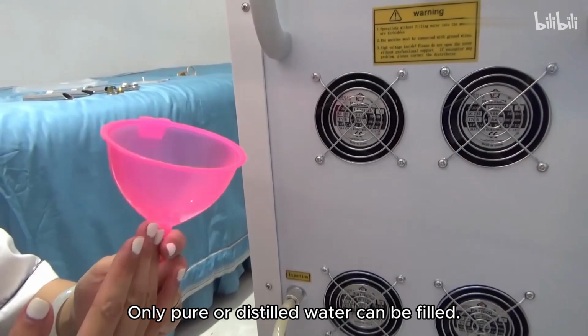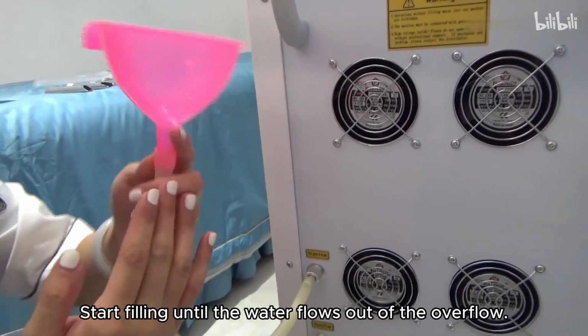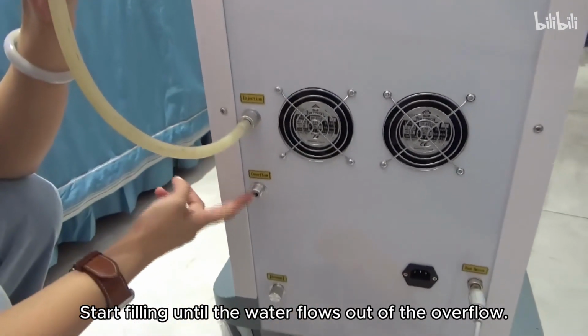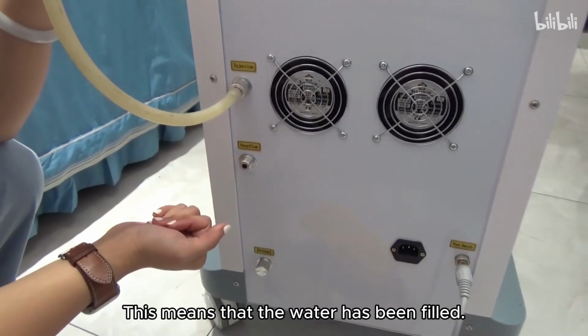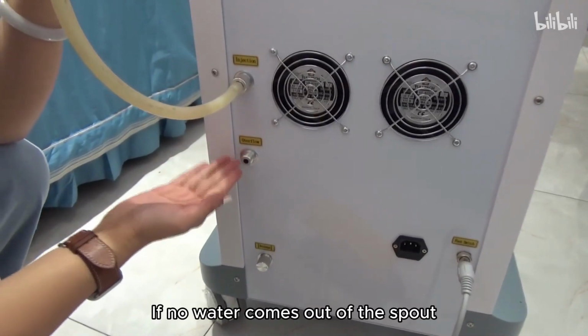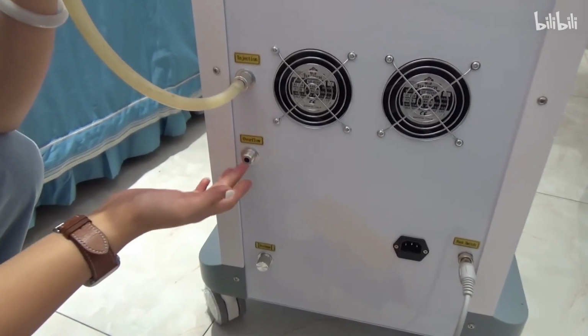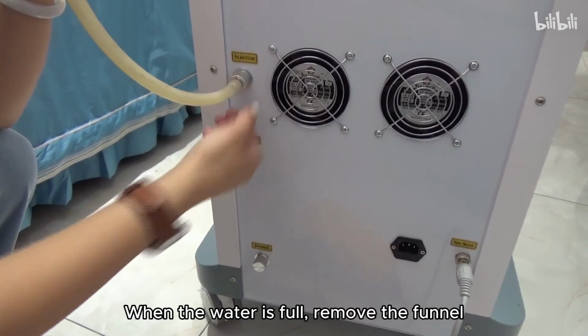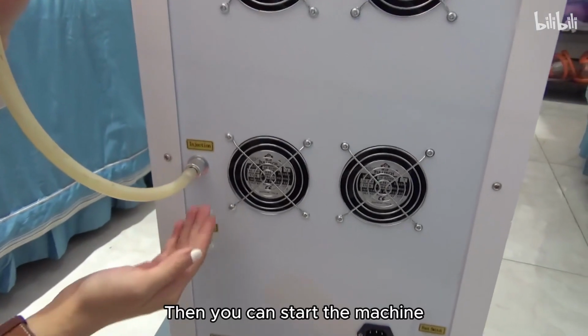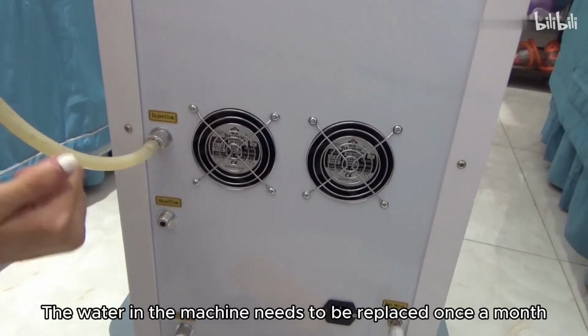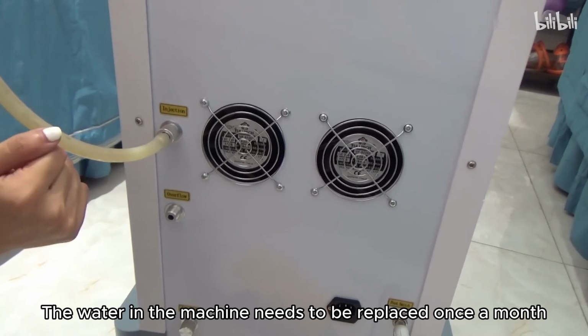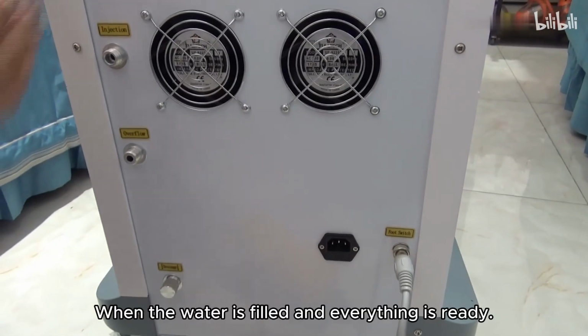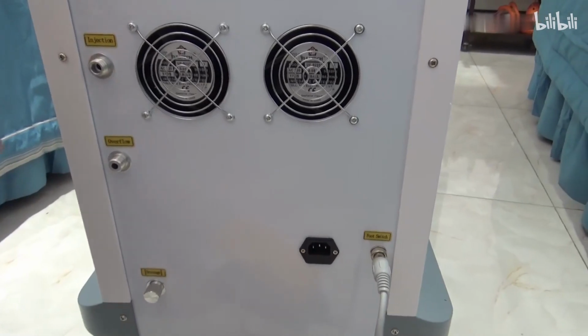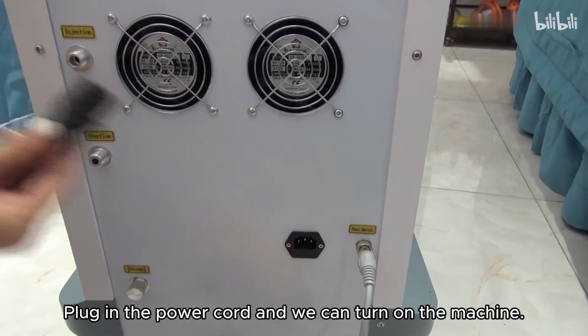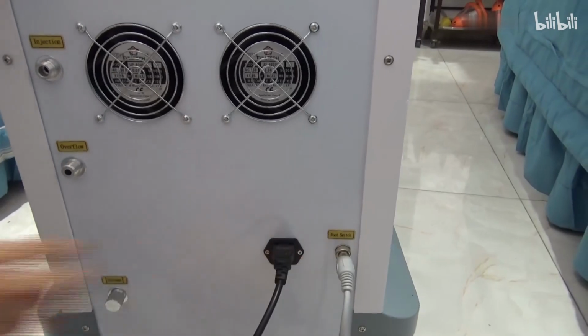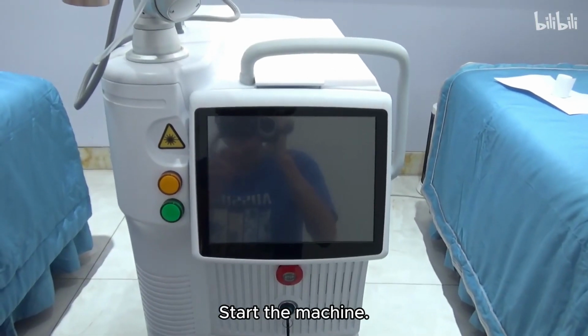Only pure or distilled water can be filled. Start filling until the water flows out of the overflow. This means that the water has been filled. If no water comes out of the spout, keep filling. When the water is full, remove the funnel. Then you can start the machine. The water in the machine needs to be replaced once a month. When the water is filled and everything is ready, plug in the power cord and we can turn on the machine. Start the machine.